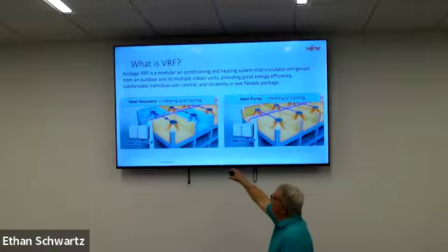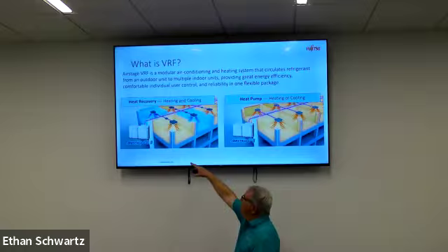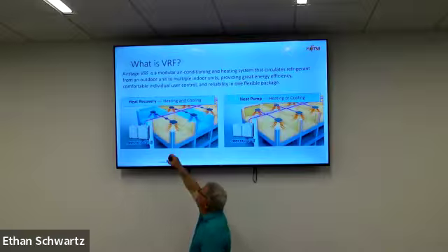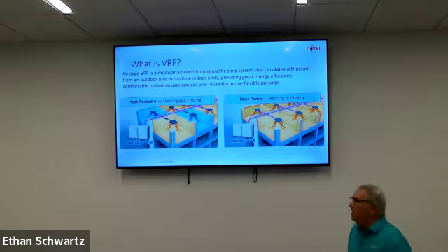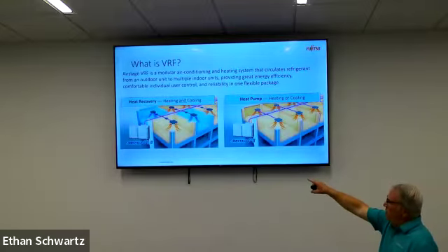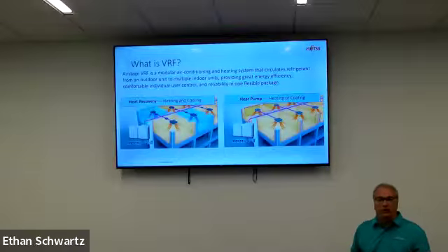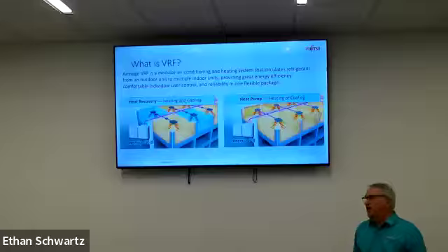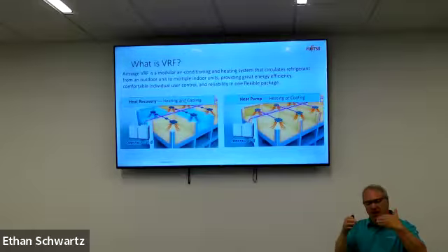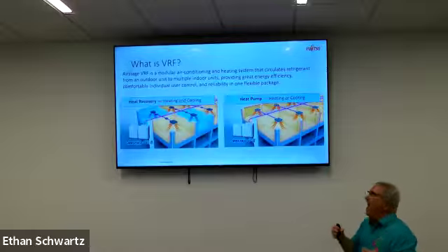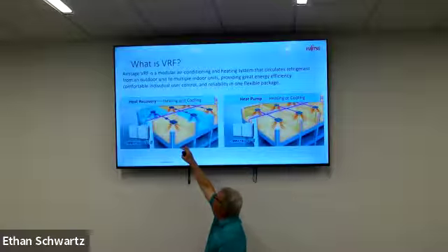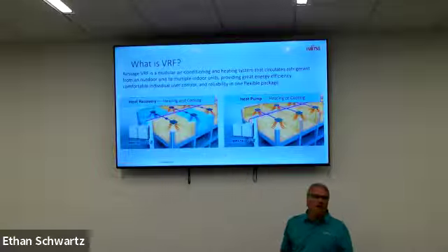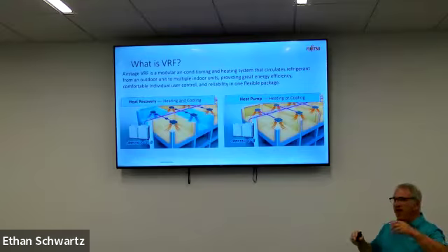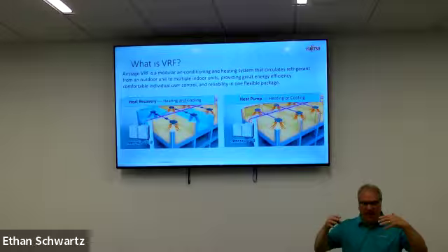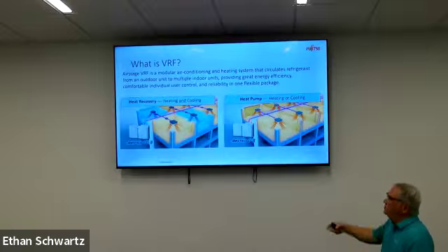And heat recovery is nothing more than condensing the hot gas off the compressor through this third component, which is called a refrigerant branch unit, others call it a branch controller. But taking the hot gas off the outdoor unit, going through solenoid valves in the RBU, and then turning that indoor unit into a condensing coil, a condenser, rejecting the heat, just like a condenser always does, and then taking that high temperature, high pressure gas back to a liquid. And then that liquid, because of pressure changes in the piping, is able to go to the next office because it's a liquid metered through the electronic expansion valve. It then begins to evaporate, and then we get cooling, just like a normal evaporator. And so that's what VRF does.